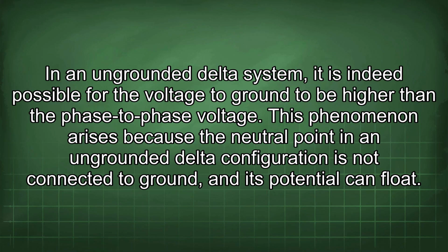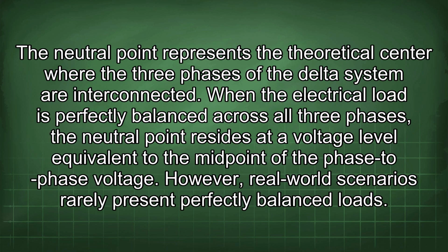In an ungrounded delta system, it is indeed possible for the voltage to ground to be higher than the phase-to-phase voltage. This phenomenon arises because the neutral point in an ungrounded delta configuration is not connected to ground, and its potential can float. The neutral point represents the theoretical center where the three phases of the delta system are interconnected. When the electrical load is perfectly balanced across all three phases, the neutral point resides at a voltage level equivalent to the midpoint of the phase-to-phase voltage.